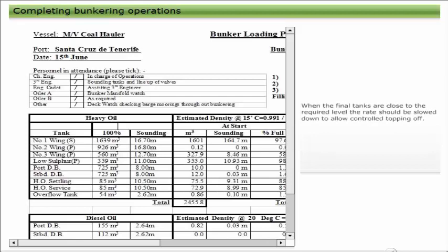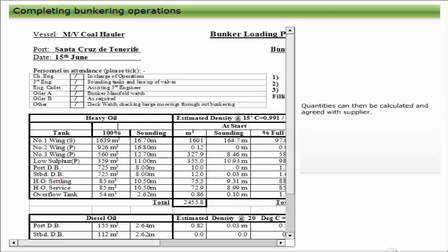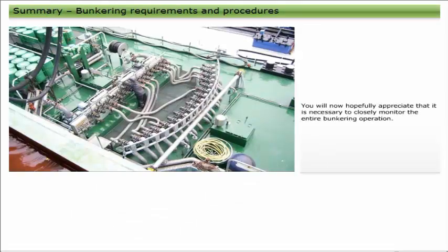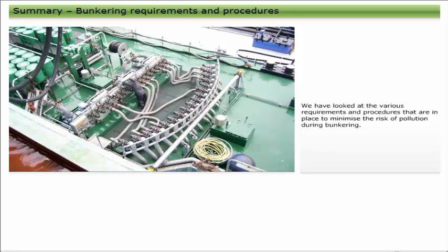When the final tanks are close to the required level, the rate should be slowed down to allow controlled topping off. The supplier should be informed and be ready to stop delivery at completion. All valves should be closed, any blanking plates refitted, and all tanks should be sounded. Quantities can then be calculated and agreed with the supplier. Since bunkering operations are the source of a majority of pollution incidents involving fuel oils, it is necessary that every precaution is taken to avoid pollution incidents. We have looked at the various requirements and procedures that are in place to minimize the risk of pollution during bunkering.